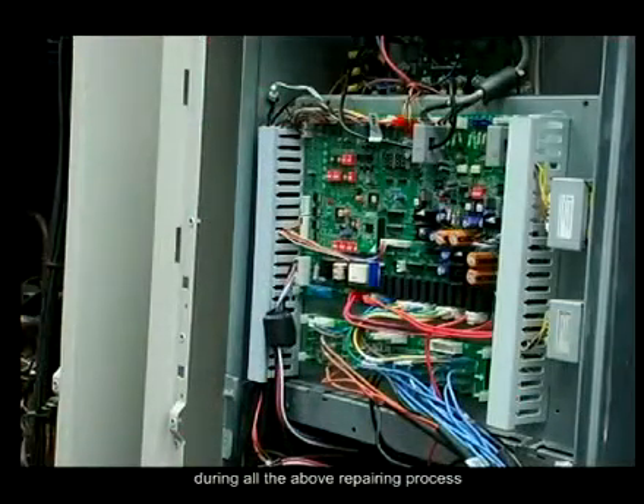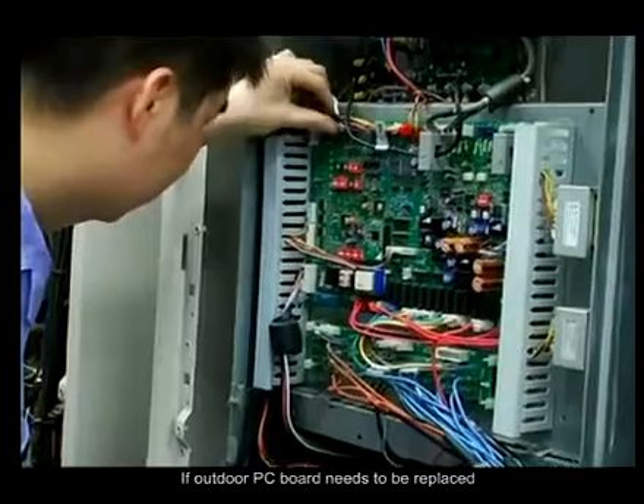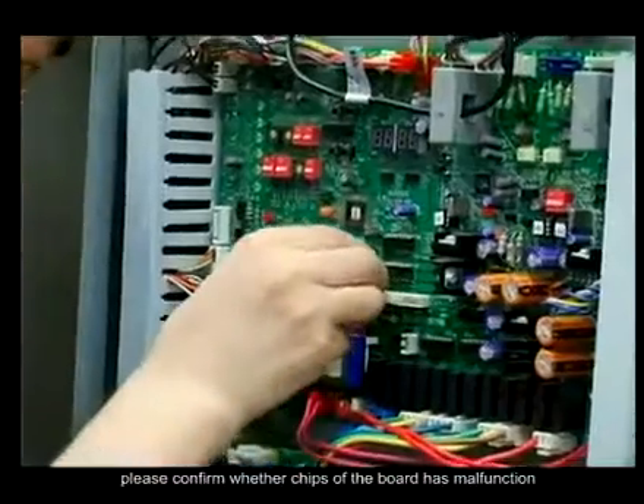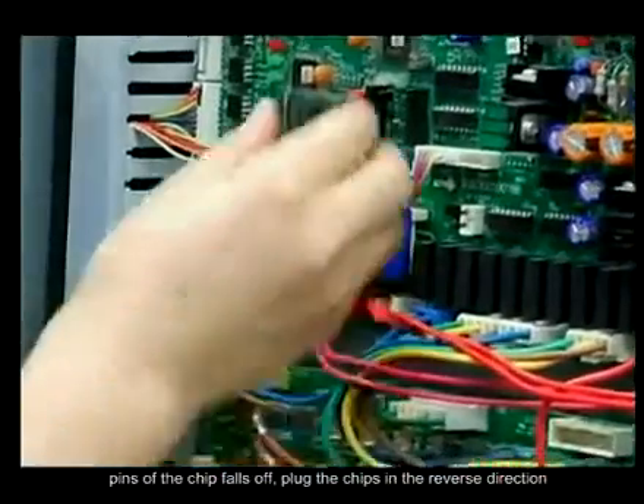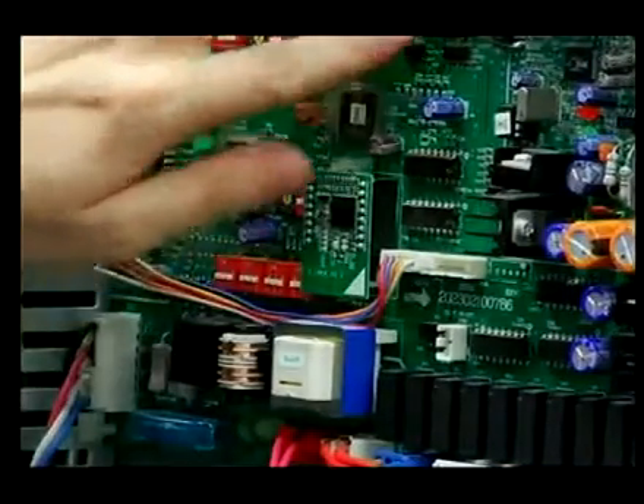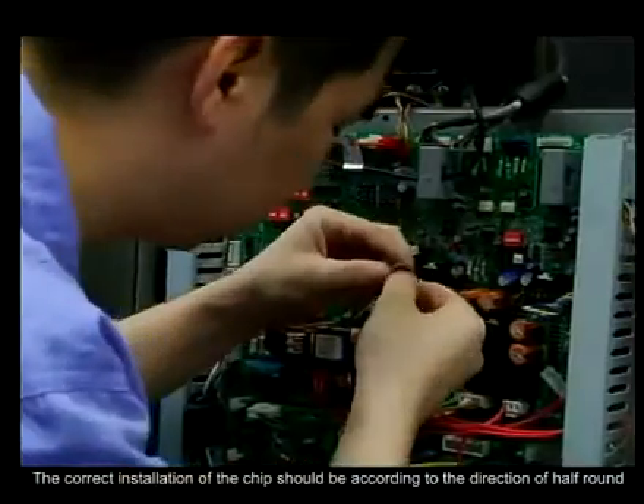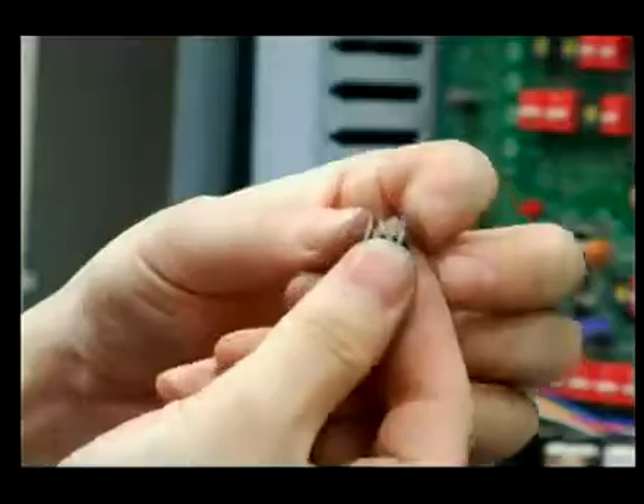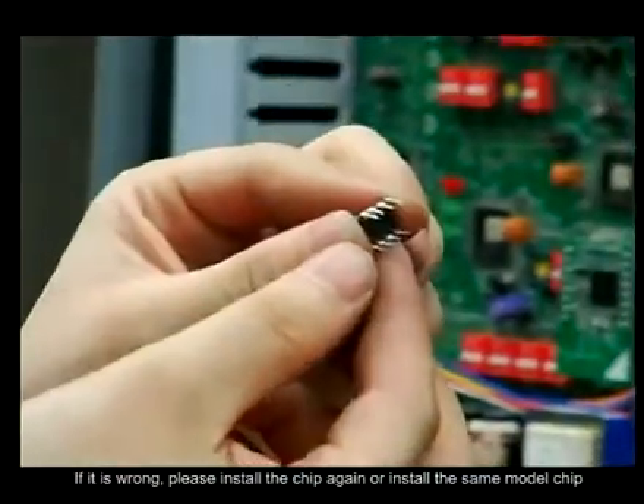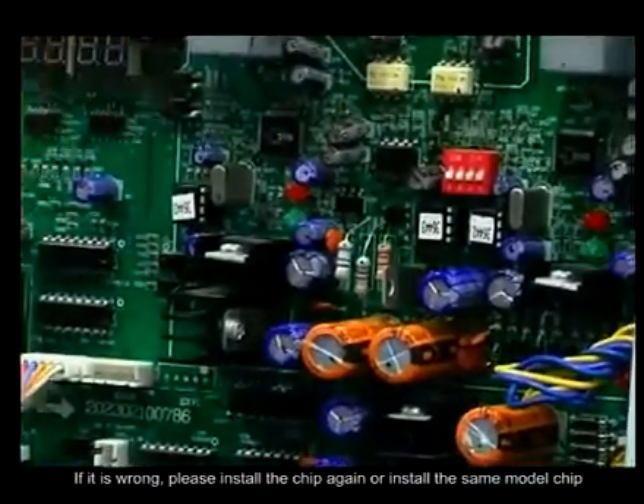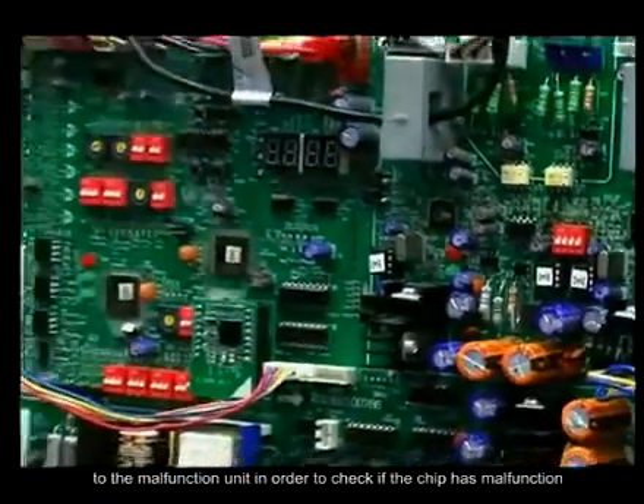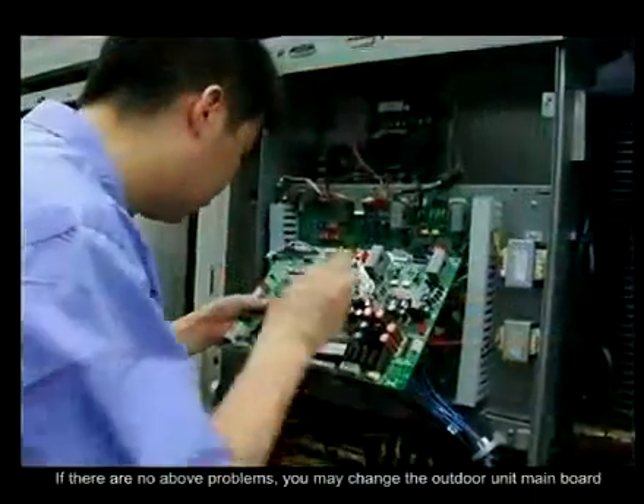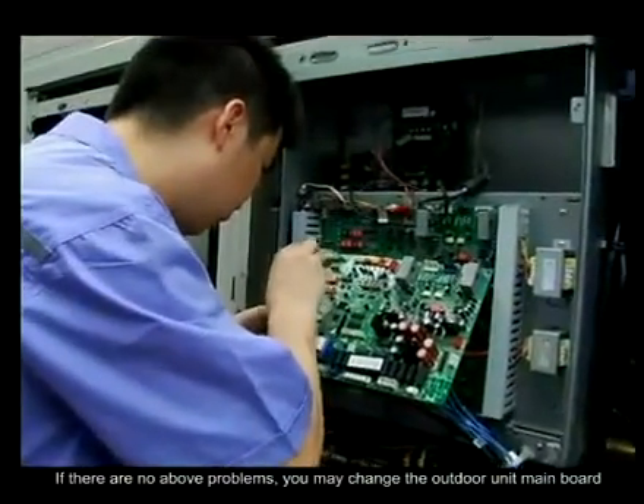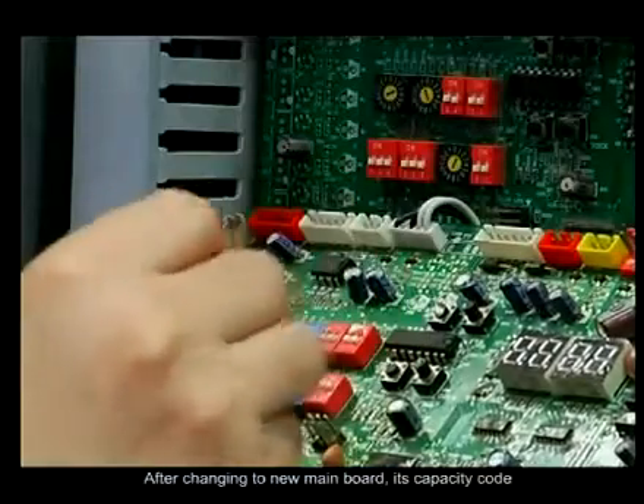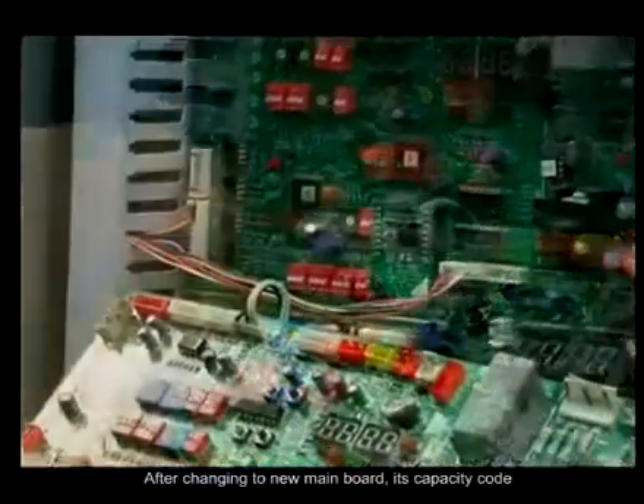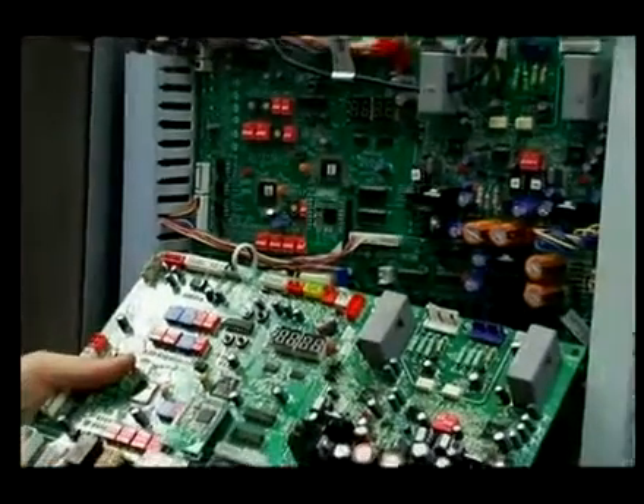During all the above repairing process, if the outdoor PC board needs to be replaced, please confirm whether the chips of the board have a malfunction. Pins of the chip may fall off, or the chips may be plugged in the reverse direction. The correct installation of the chip should be according to the direction of the half round. If it is wrong, please install the chip again, or install the same model chip to the malfunction unit in order to check if the chip has a malfunction. If there are no above problems, you may change the outdoor unit main board. After changing to a new main board, its capacity code and address code must be the same as before.